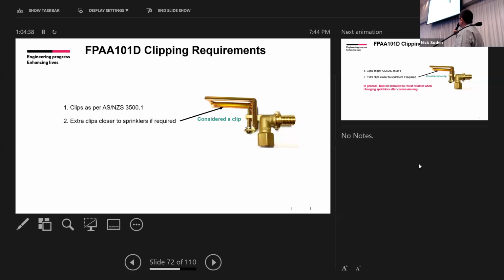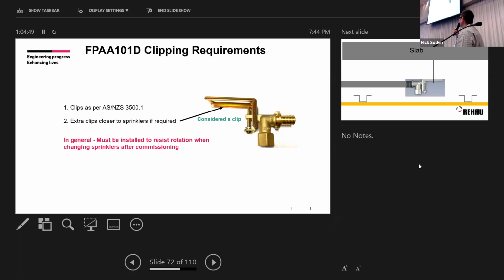Now clipping. Clipping is according to the standards, and Rehau has recommendations in our technical information as well. Extra clips close to sprinklers are available if required, because you can clip onto our pipework. But in general, they must be installed, so that during removal and replacement of sprinkler heads there's no rotation of the pipe and fittings. By having the clips, the M10 section, the bracket section, and the pipe on opposite ends, the pipe is very stiff. I can get you guys to come up and have a play with these fittings after, and you can feel the resistance. It is going to be a really good fixed joint as well.